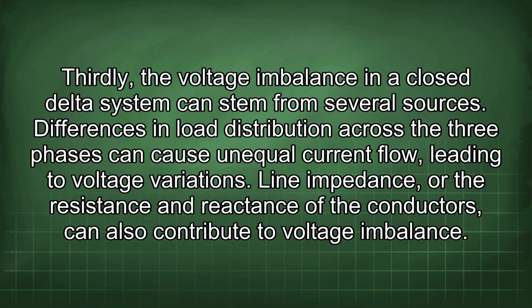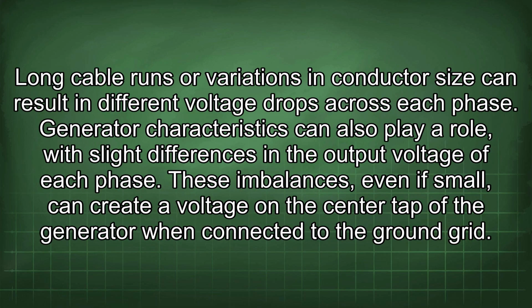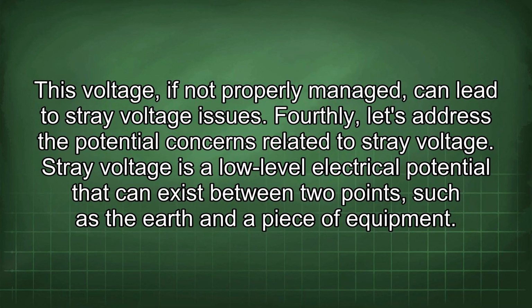Thirdly, the voltage imbalance in a closed delta system can stem from several sources. Differences in load distribution across the three phases can cause unequal current flow, leading to voltage variations. Line impedance, or the resistance and reactance of the conductors, can also contribute to voltage imbalance. Long cable runs or variations in conductor size can result in different voltage drops across each phase. Generator characteristics can also play a role, with slight differences in the output voltage of each phase. These imbalances, even if small, can create a voltage on the center tap of the generator when connected to the ground grid. This voltage, if not properly managed, can lead to stray voltage issues.